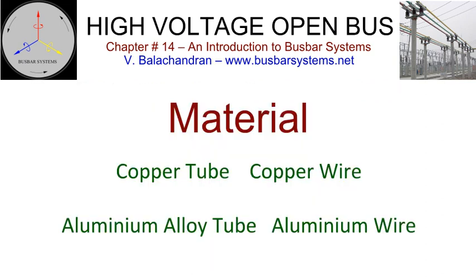Material. The conductor materials used in a switchyard are copper or aluminium in the shape of copper tube, copper wire, aluminium alloy tube, aluminium wire, all aluminium conductor, AAC, all aluminium alloy conductor, AAAC, aluminium conductor alloy reinforced, ACAR, and aluminium conductor steel reinforced, ACSR. Of these, aluminium alloy tubes are the most preferred and are the most commonly used material in switchyards.